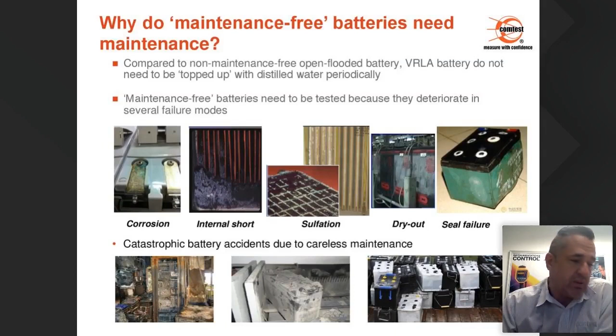So what affects a battery? Low temperatures slow down the internal chemical reactions in any battery. If a battery room's ambient temperature is higher than 25 degrees Celsius, the floating current demand on your charger will be doubled for every 10 degrees Celsius increase in the electrolyte temperature.